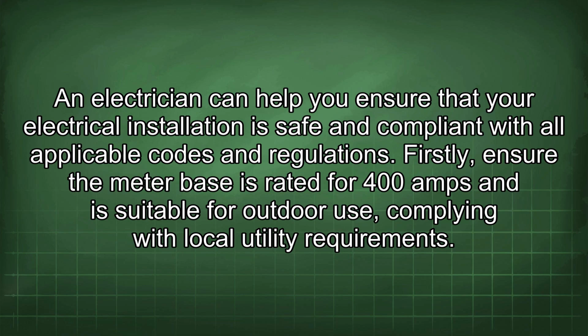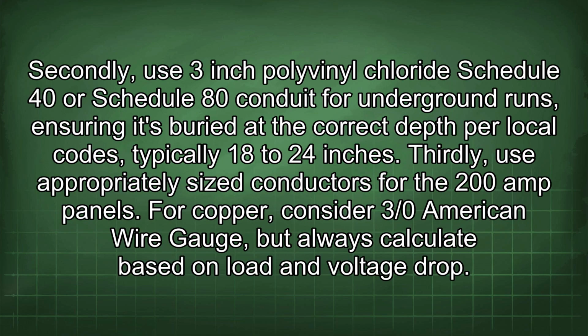Firstly, ensure the meter base is rated for 400 amps and is suitable for outdoor use, complying with local utility requirements. Secondly, use 3-inch polyvinyl chloride Schedule 40 or Schedule 80 conduit for underground runs, ensuring it's buried at the correct depth per local codes, typically 18 to 24 inches.